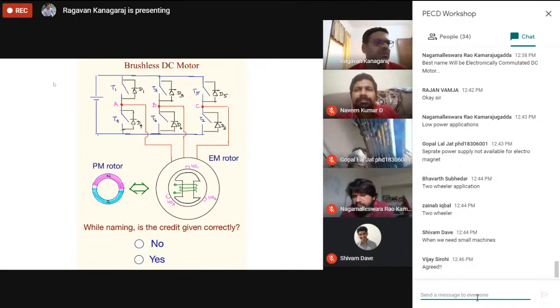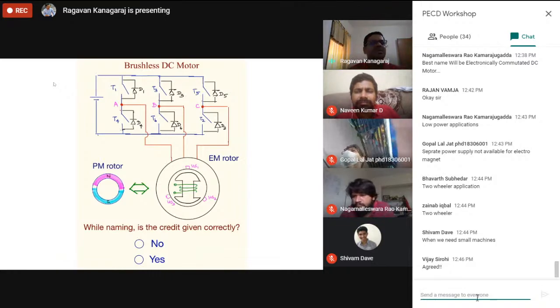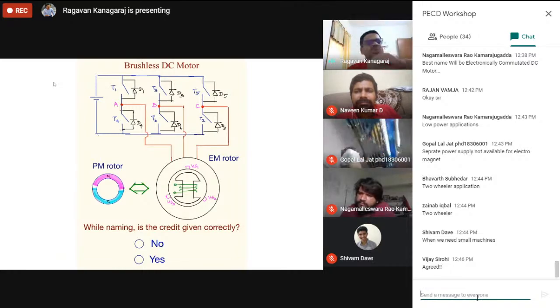Okay. And sometimes what happens, whenever you want to carry out a maintenance operation, if it is an electromagnet, you will switch off the winding. And the winding also will have some remnant residual flux density in the machine. So you can do some short circuiting. And finally, you can ensure that the system is free from residual flux and you can comfortably work. But when magnets are sitting there, now you want to do some maintenance activity in the stator winding, for instance, right? Now you will carry some iron, whatever instrument you are carrying. So there is a high possibility that it will get attracted.